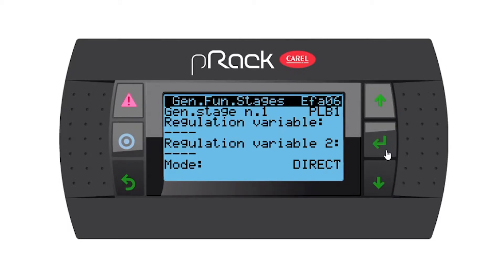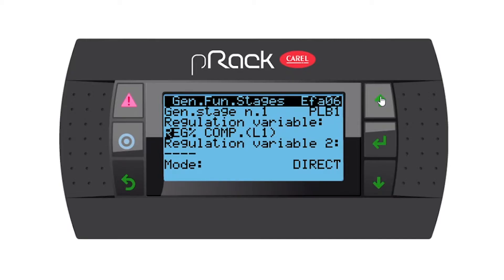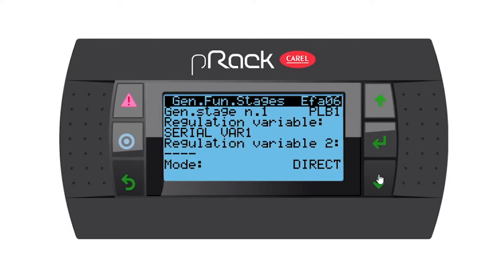Let's enter — you have a couple of options: power percentage compressors, power percentage fans, line one regulation percentage compressors, line one regulation percentage fans, serial variable one, or serial variable two. I'd like you to use serial variable one. We don't have a secondary variable, so we're only going to use one probe.